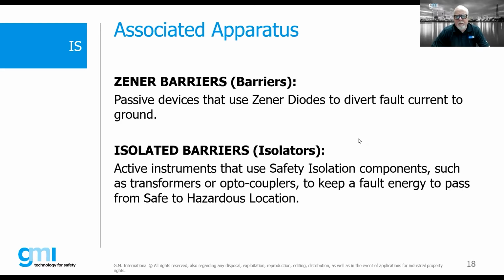Along, however, came isolated barriers or isolators, which we call galvanically isolated. There's many different terms, and we all kind of use similar concepts, but basically, an isolated barrier is similar in concept to a Zener barrier, except there is some sort of isolation component inside, such as a transformer or an optocoupler, to keep fault energy from passing from a safe to a hazardous location. Where a Zener barrier is a direct connect device between our control panel output and the end device, an isolated or galvanically isolated barrier has an extra step, and it's more or less repeating the signal.